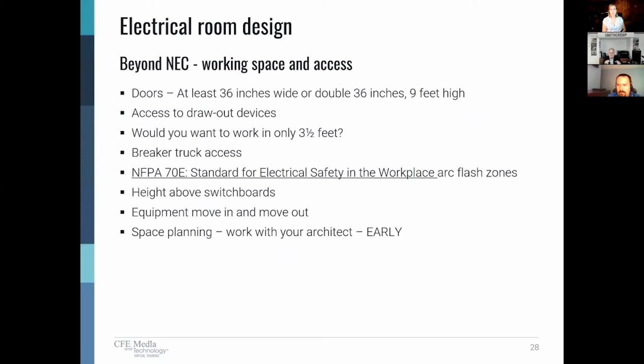How's it going to all fit within the room? But how are you going to get it in and out of the room? So those 36-inch wide doors will get breakers out or equipment out or replacement parts. I recommend at least 36 inches wide, double doors, 9 feet high. So that's significantly higher than what the National Electrical Code's asking. In the new code, they start understanding the need to access draw-out devices and not impede that.